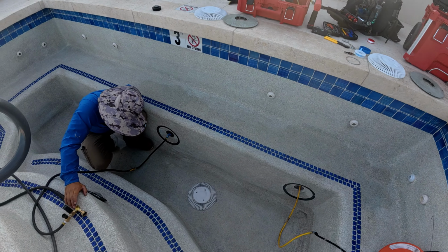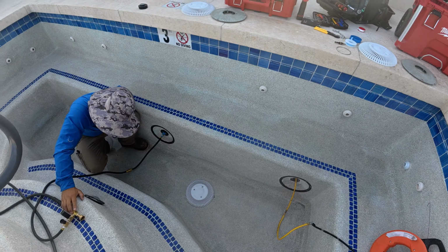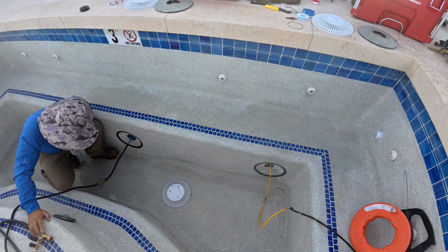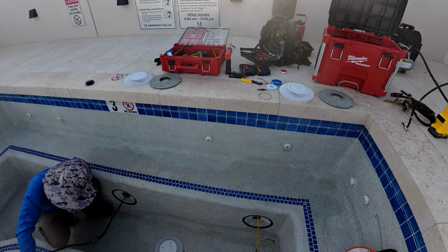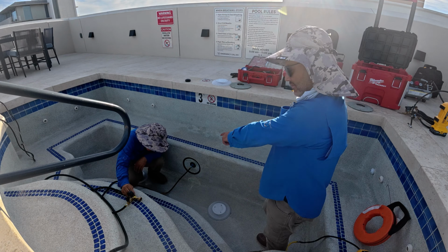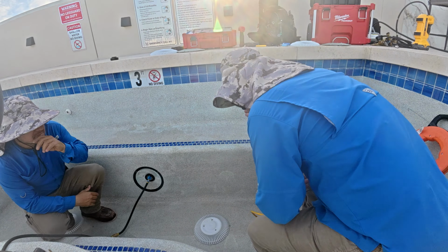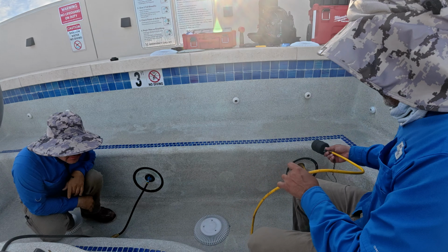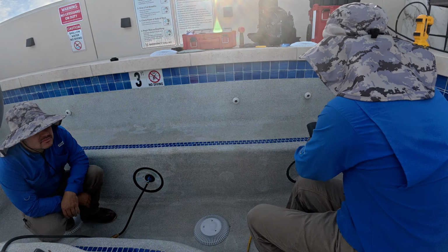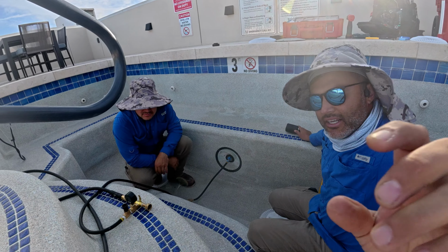And now what we're trying to do is have sections that we're testing the line, and the way that we're doing that, we'll definitely show you in a moment. What we're doing now is testing this particular line from here all the way to here. We have a plug similar to this one that we fish taped all the way to pretty much right here, and then we're introducing air.